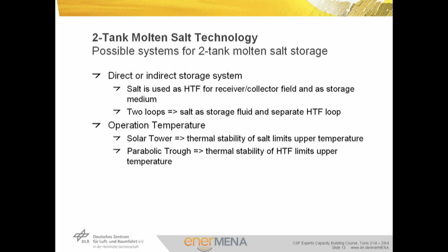There are two different basic options for implementing two-tank molten salt storage systems. In direct storage systems, molten salt is used both as heat transfer fluid in the solar absorbers and as storage material. In indirect systems, the heat transfer fluid in the absorbers is different from the molten salt used in the storage. The decision between direct and indirect systems depends on the operation temperature of the CSP facility. In today's parabolic trough systems, thermal oil is used in the absorbers, so two separate loops are used. In central receivers, molten salt is also used as HTF, so direct storage can be applied.